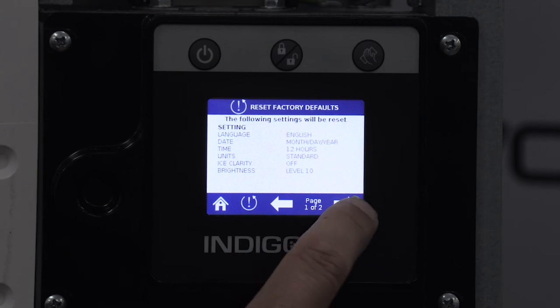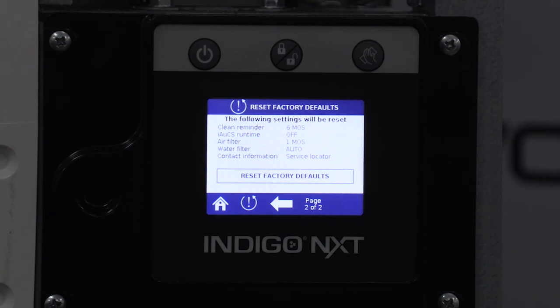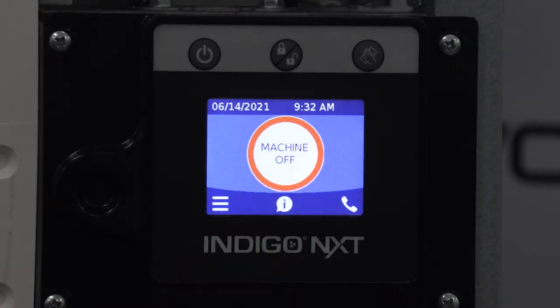Press the right arrow again to see the second page, which resets: clean reminder to 6 months, iAUCS runtime to off, air filter reminder to 1 month, water filter reminder to auto, and contact information set back to the QR code link for Manitowoc Ice's online service locator. If you choose not to reset the ice machine back to factory defaults, press the home icon and the screen will change back to the home screen.